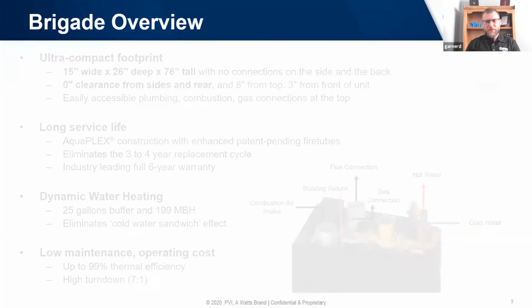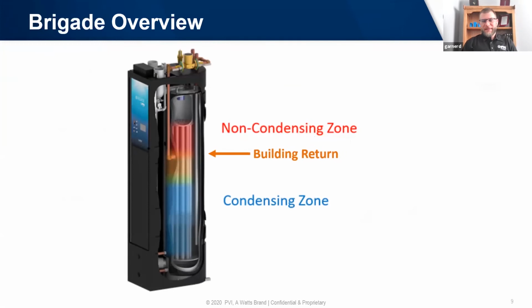The unit itself has a 7-to-1 turn down ratio. We also have a dedicated recirc connection. And what that does is it takes the hot water coming back from the building and ties it to the warm or hot part of the heat exchanger. So we don't preheat any of the cold water coming into the unit. So we're not sacrificing any efficiency when we're going through the whole condensing efficiency curves.